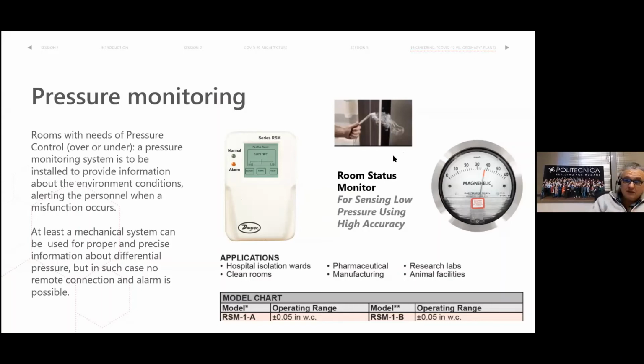But at the end of the story, there is also this check that has to be made with a smoke. You can do it even with cigarettes. This is very important because you can see in a visible way how everything is working, if the distribution of the air is okay. It is not a quantitative, but it is a qualitative check. But it is even important. If you have a certain experience, just with the smoke test, you can understand if everything works well, at least preliminarily. Then you have to do the measurement and whatever, but you immediately understand if everything works.